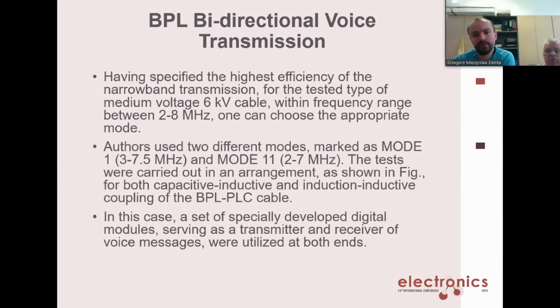The last type of experiment was the BPL bidirectional voice transmission. We identified the highest efficiency of the narrowband transmission for the tested type of medium voltage, 6 kilovolt cable, and we used the frequency range between 2 and 8 megahertz. We used two different modes using OFDM cable. Mode number 1 was from 3 to 7.5 megahertz, and mode 11 from 2 to 7 megahertz. The test was carried out in an arrangement, and in the next slides we will see both capacitive and inductive coupling and inductive coupling for the BPL PLC transmission.